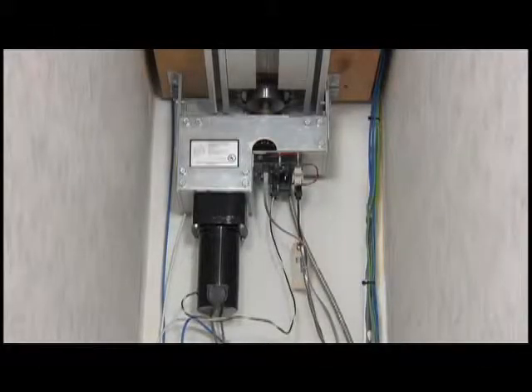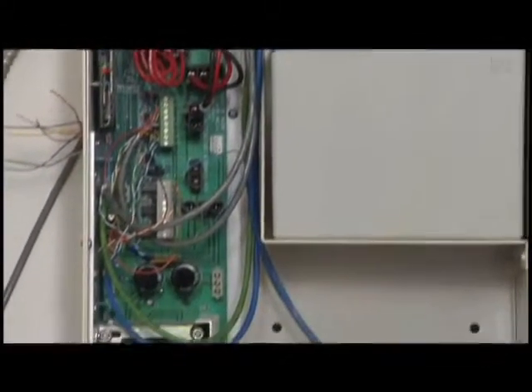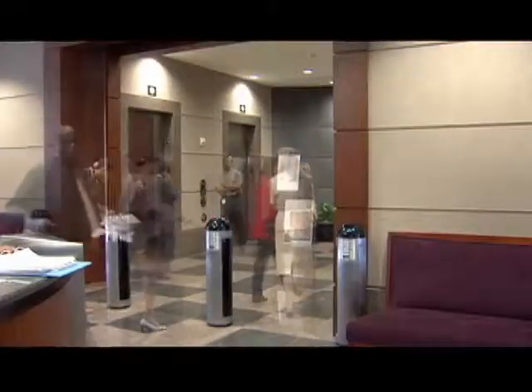The automatic closing system consists of a DC motor, battery, a transformer, and a microprocessor and logic board. This system is protected within a fire-rated enclosure and is typically located at the back of the door storage pocket. The in-house electrical system provides power to continuously charge the battery and allow the system to be completely electronically supervised. With the advent of microprocessor technology and electronic supervision, the WonDoor FireGuard door can offer a unique feature, ensuring its constant state of readiness to respond in a fire emergency.